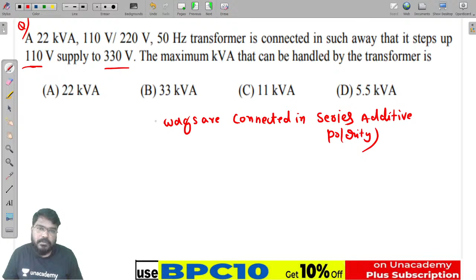Very good, so K is 1 by 3. Next, find the kVA of the auto transformer, which equals 1 by (1 minus K) times the kVA of the two winding transformer. With K equal to 1 by 3, and kVA equal to 22 kVA.